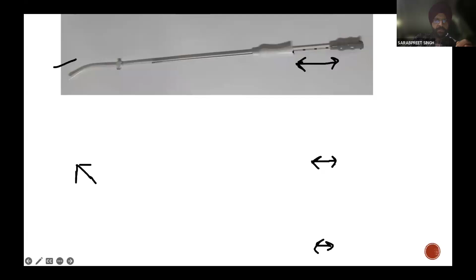I'd like to highlight that the inner and outer cannula are designed in a way that when you enter the inner cannula into the outer cannula, at the point where the first marking is there, the catheters are level. Both the tips are at the same place. When you go 1 centimeter in, the inner cannula comes 1 centimeter out of the outer cannula. When you go 2 centimeters in, the inner cannula comes out 2 centimeters from the distal end.